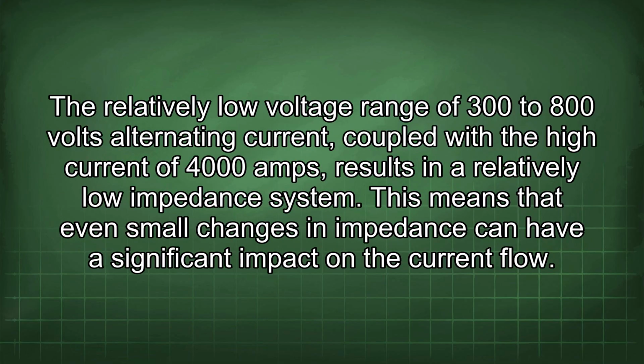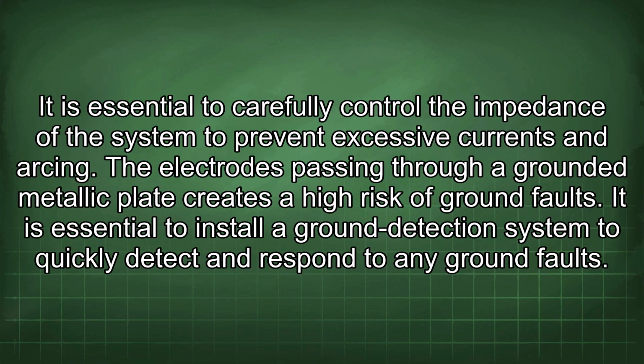The relatively low voltage range of 300 to 800 volts alternating current, coupled with the high current of 4000 amps, results in a relatively low impedance system. This means that even small changes in impedance can have a significant impact on the current flow. It is essential to carefully control the impedance of the system to prevent excessive currents and arcing.